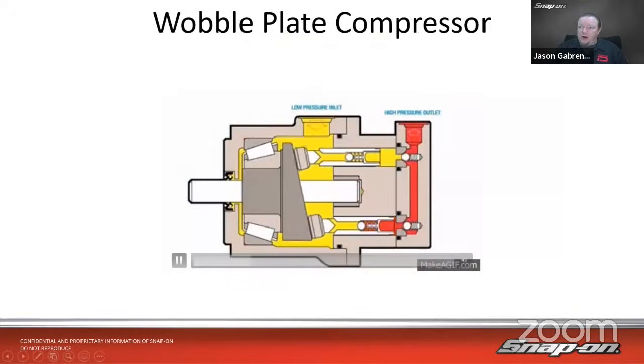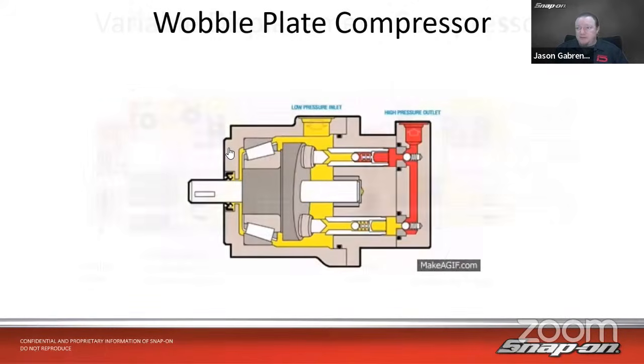All right, and then a wobble plate compressor has a wobbly shaped plate, which is a little bit different. Then the low pressure comes in, and we have these springs here as well. So it allows some of that pressure to go in, and then it compresses it. Then there's another ball and check there, and it goes out to high pressure. So there are a couple different ways you can go about it between the swash plate and the wobble plate.